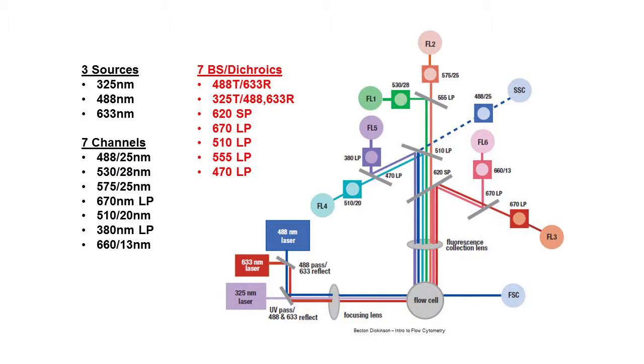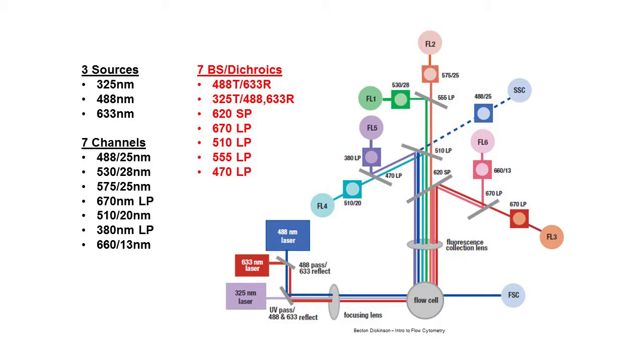So we'll look at two quick examples, two schematics from Becton-Dickinson. In this case, we're looking at the LSR flow cytometer. It's a bit tough to follow, but if you take a close analysis here, there's ultimately three sources, seven channels, and over 14 filters in this system. Again, these are all very tightly controlled bandpass filters, beam splitters, and dichroic style filters.